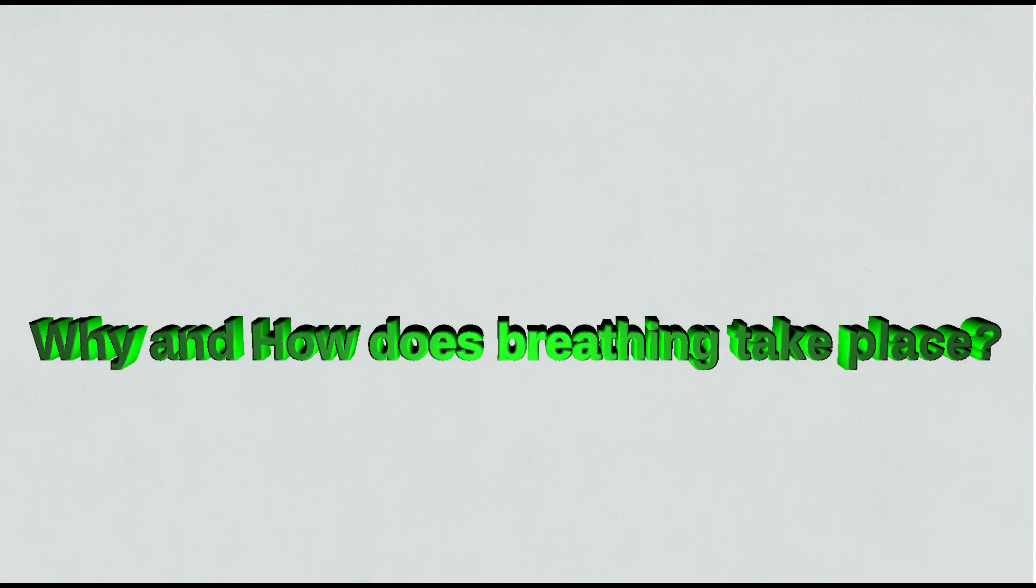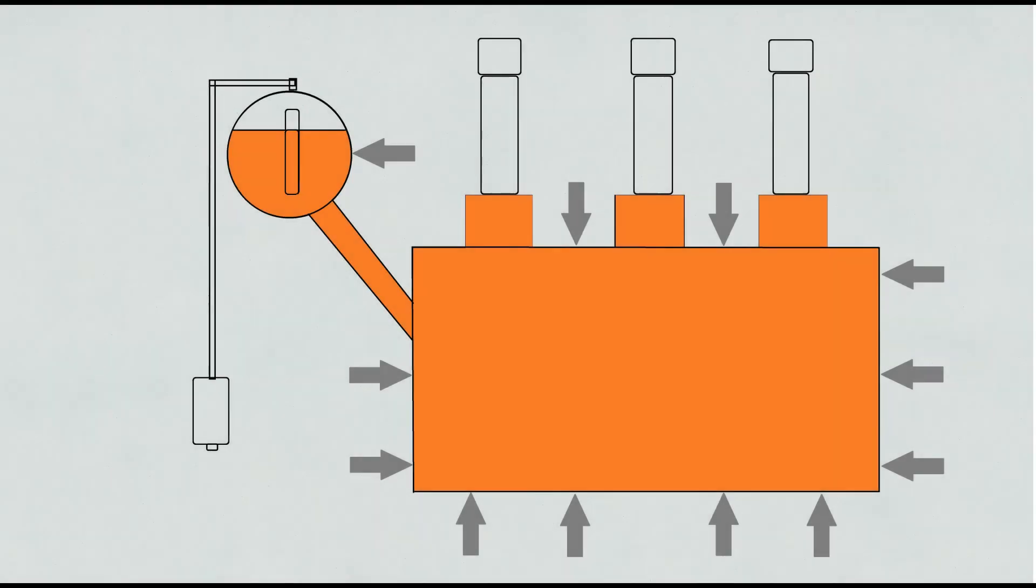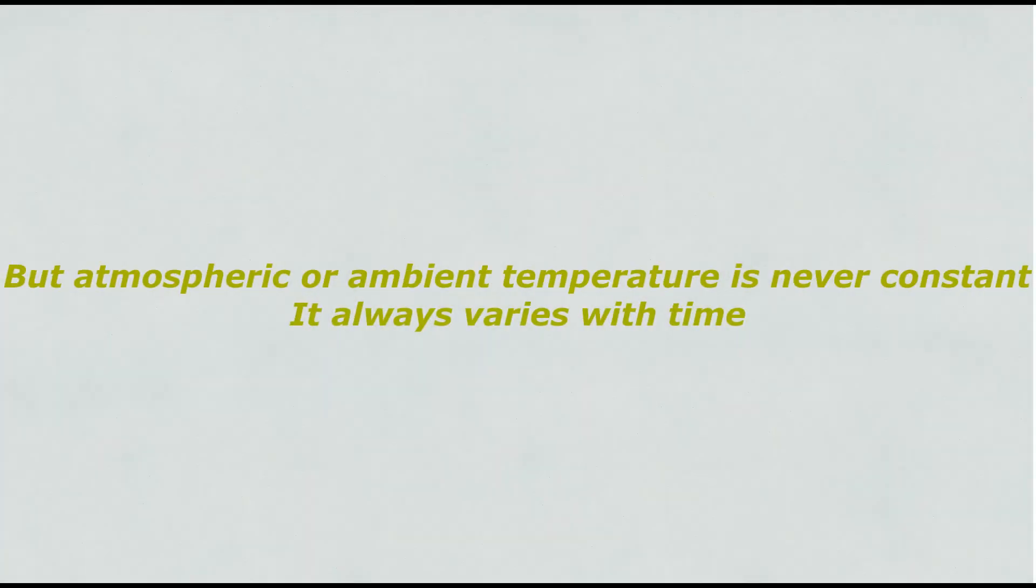For the second and third questions, why and how does breathing take place? As we know, a transformer is an airtight machine completely filled with insulating oil, meaning there is no way to pass air in or out of the transformer. But atmospheric or ambient temperature is never constant. It always varies with time.